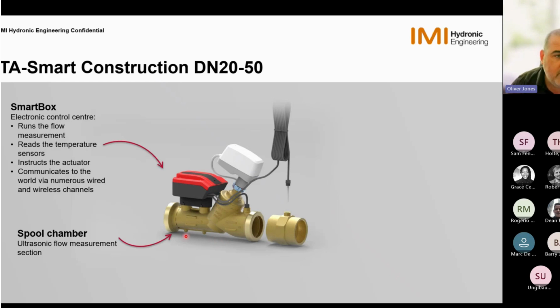We then have the spool chamber, which is our ultrasonic flow measurement section. So this is where our flow is being measured. Typically we use the time of flight principle. So we're measuring the flow with the pressure and against the pressure, because obviously with the pressure the flow would be faster and against it would be slower. So we take an average of these two together and it gives us a very accurate flow measurement.